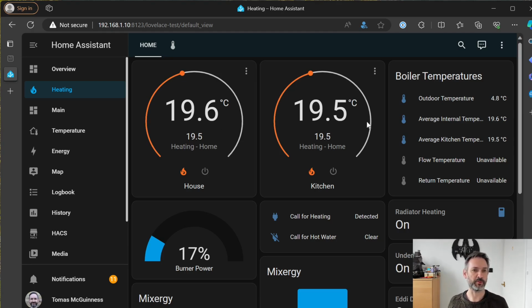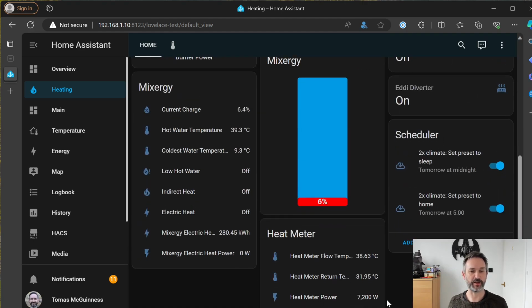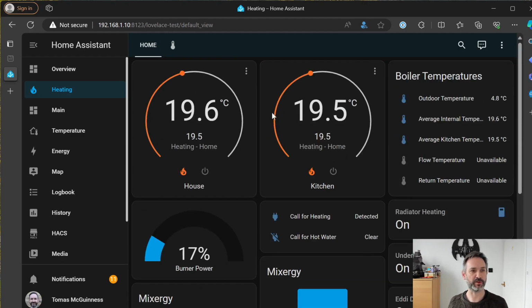So if we couple that, we will simply have our indoor and outdoor temperatures. We've got our heat meter reading the input, and I'm hoping that the input from the boiler will drop down to its minimum, because it will try to keep the flow temperature sitting around 40, so it won't be putting in too much heat, and the heat loss should be great enough to maintain a temperature under 22. That's the theory anyway.